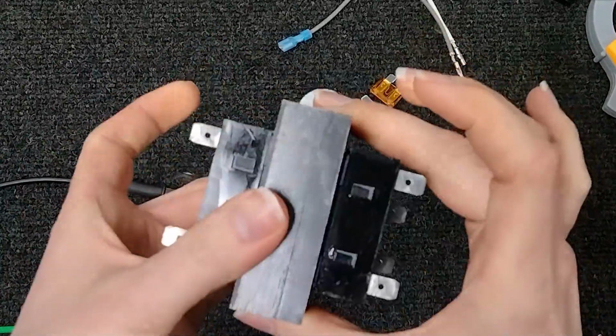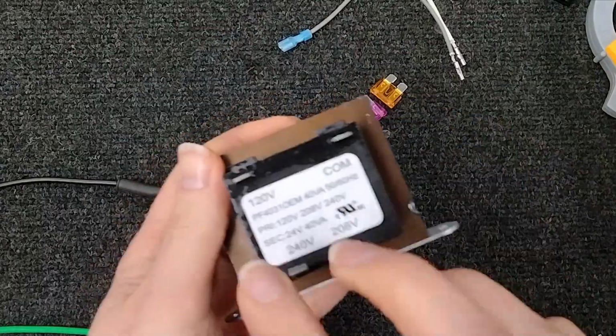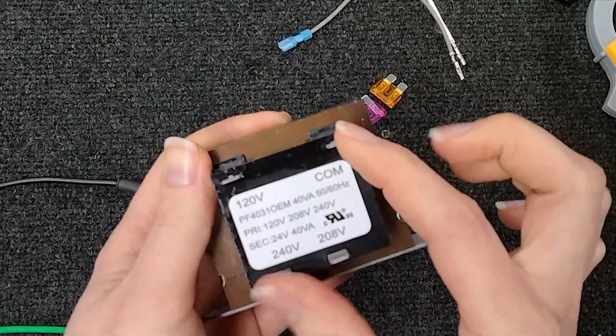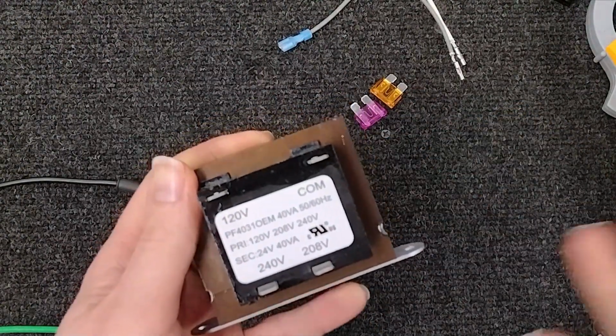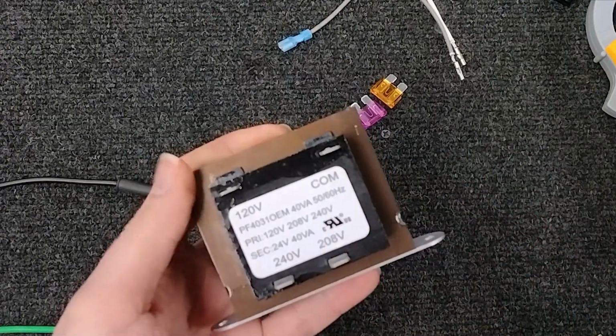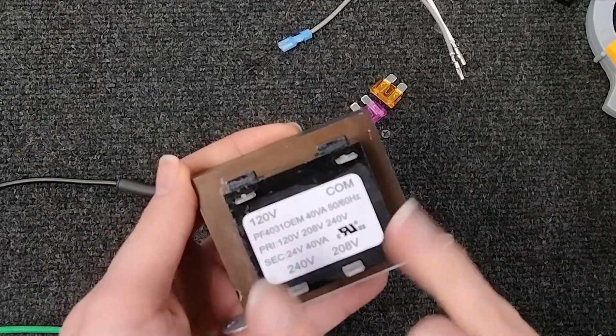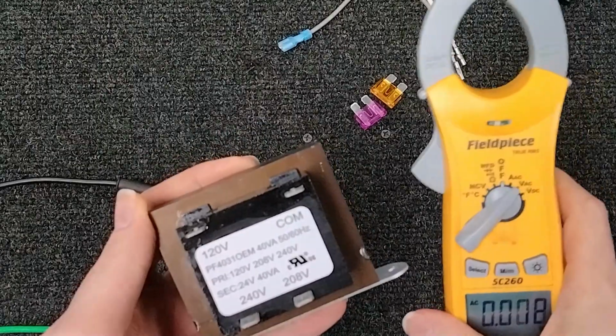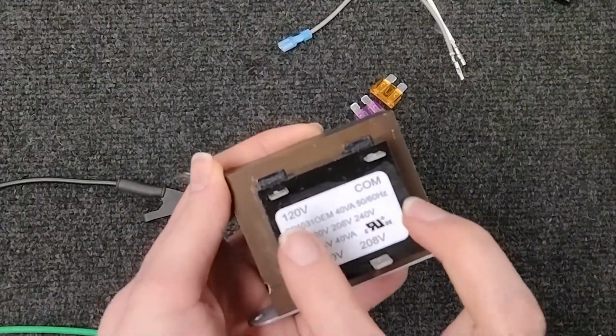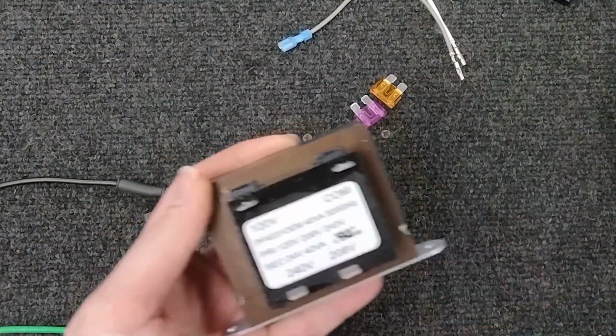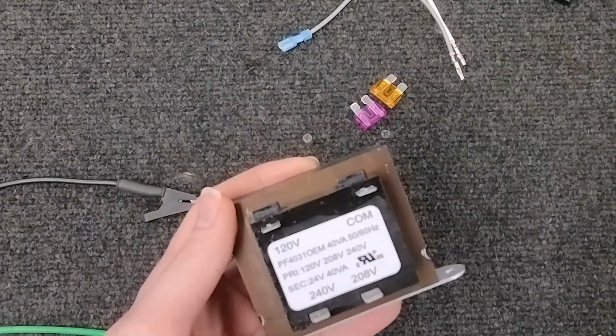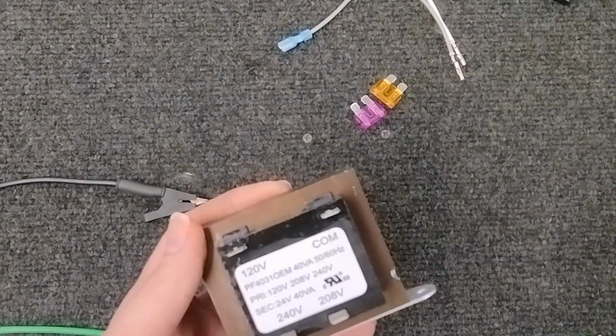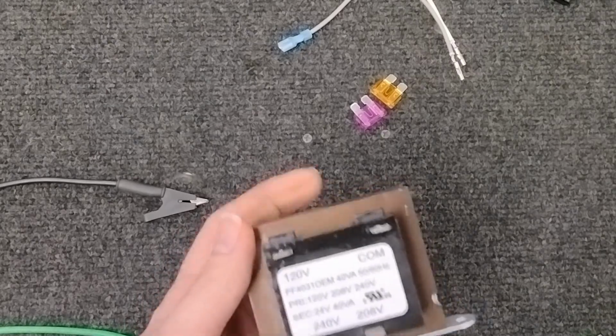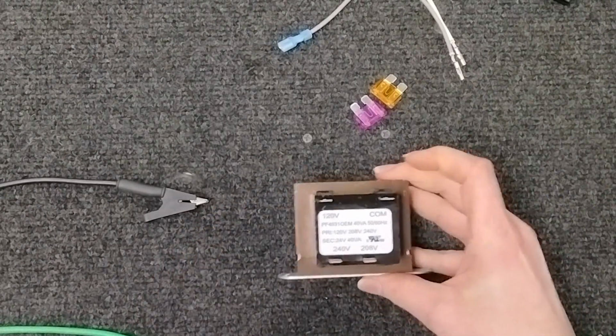It could be angled in there different. But this is where your main power, your high voltage, is going to be coming through. So your high side here, what you're doing is you're going to put your voltmeter on one of each of these legs. Again, make sure you are not testing against ground because you can get some feedback.